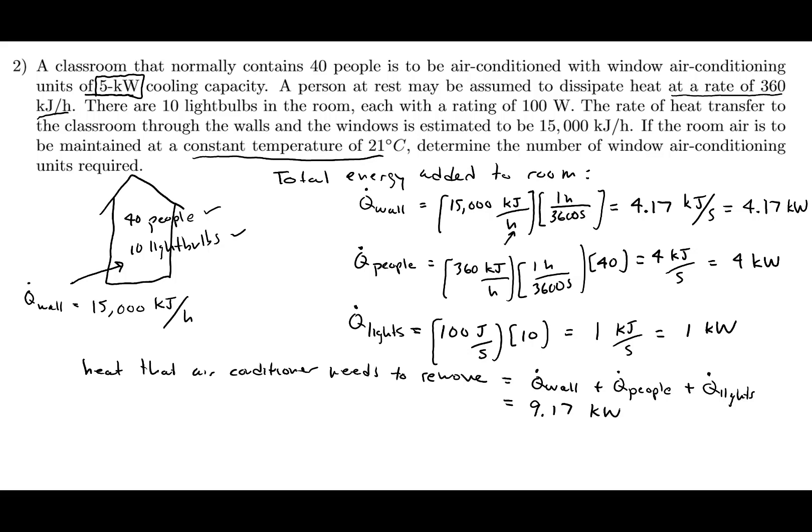We know that the capacity of each air conditioner is 5 kilowatts. It's asking us how many air conditioners we need. So we just take the amount of heat that we need to remove, which is 9.17 kilowatts, and divide it by the capacity of the air conditioner, which is 5 kilowatts. This works out to 1.83, so that means we need 2 units. We need 2 AC units.